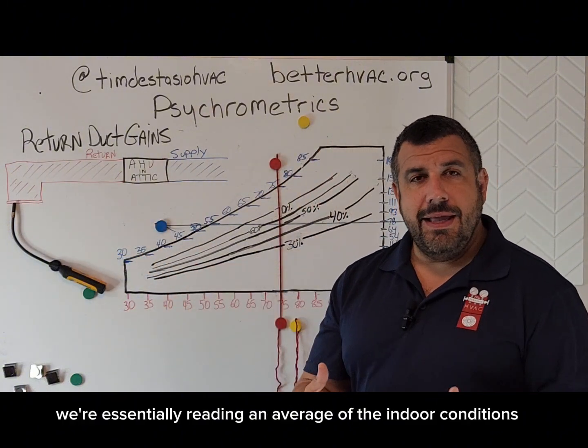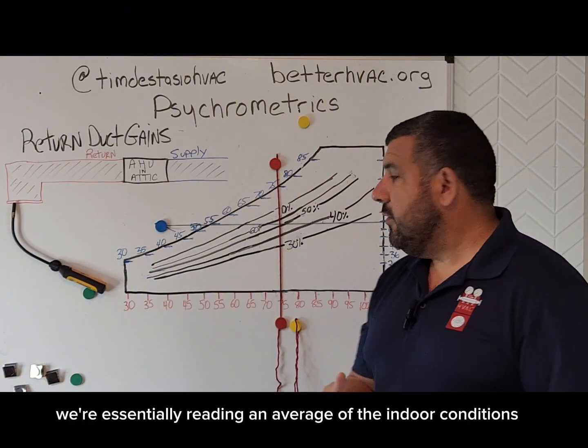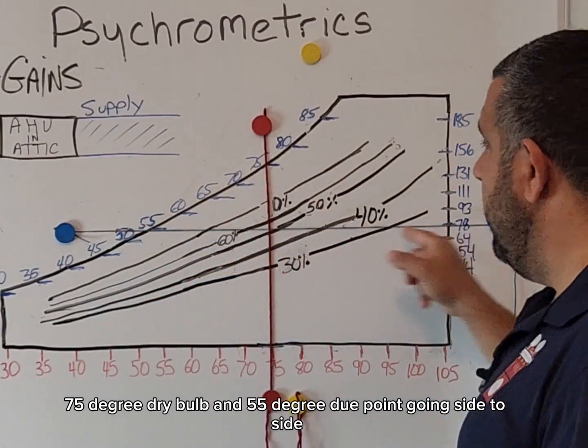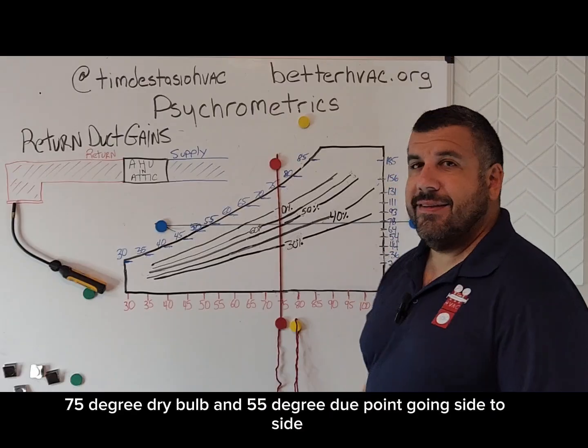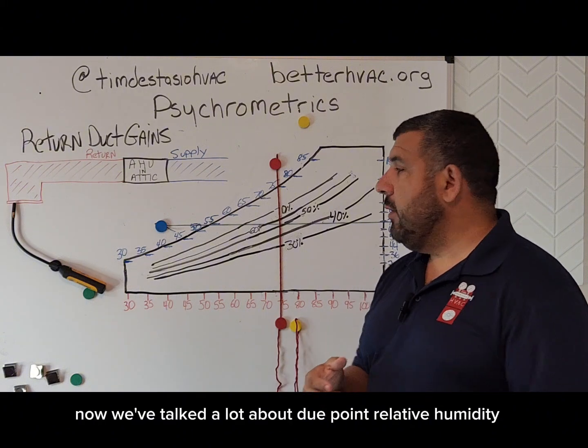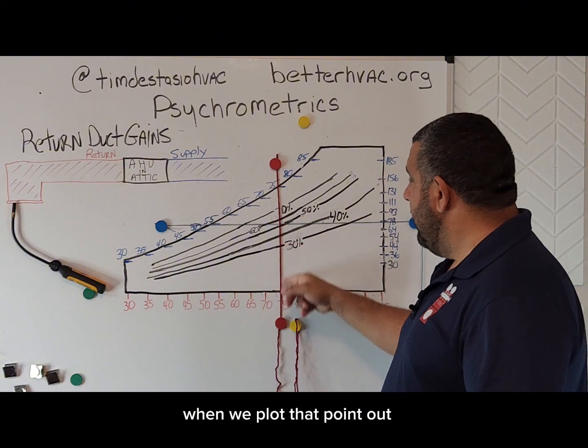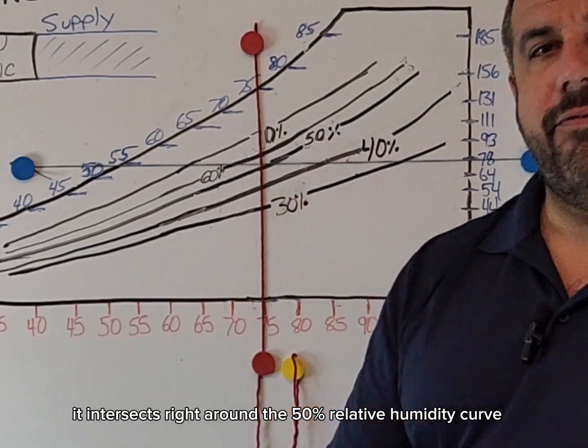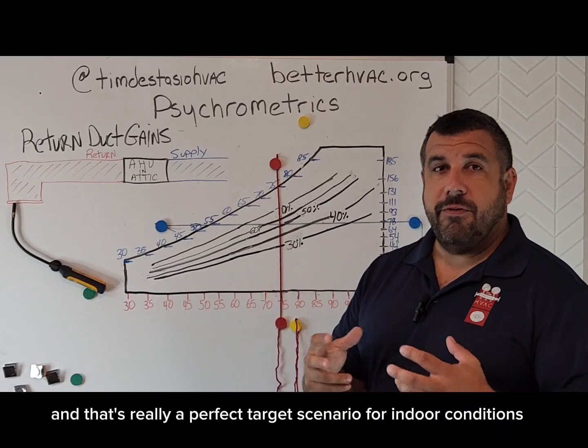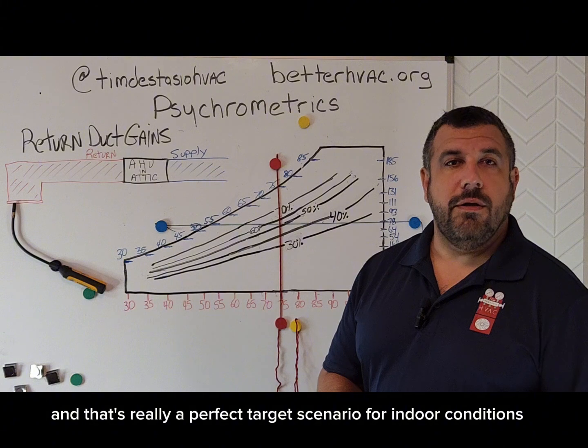Now, let's say that we plot a point here measuring at the return grille, the return inlet. We're essentially reading an average of the indoor conditions, 75 degree dry bulb and 55 degree dew point going side to side. Now, we've talked a lot about dew point, relative humidity. When we plot that point out, it intersects right around the 50% relative humidity curve. And that's really a perfect target scenario for indoor conditions.